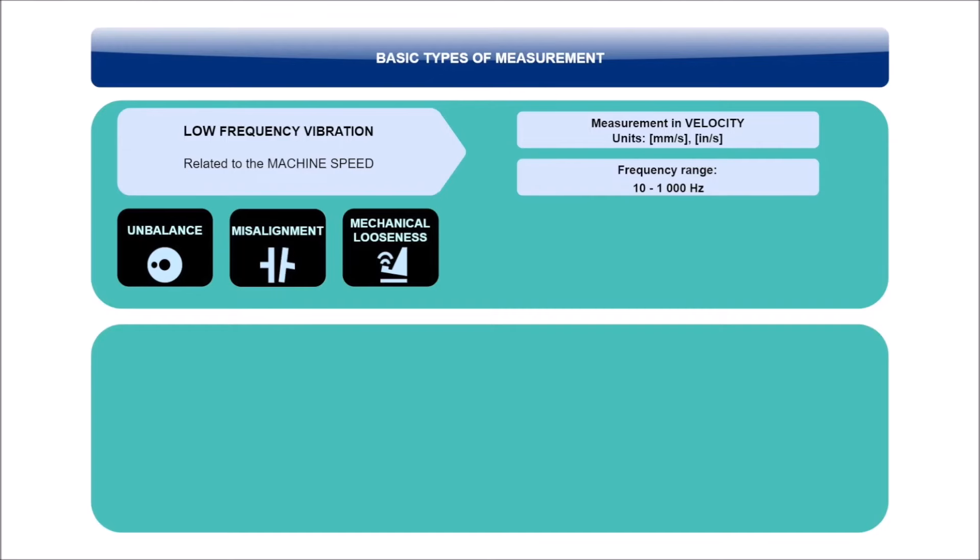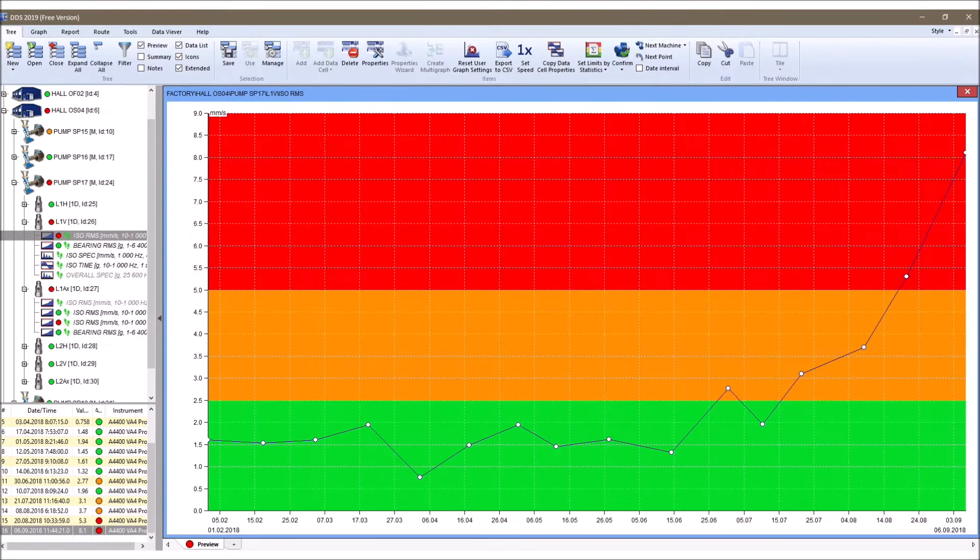This way we came to the conclusion that to monitor mechanical vibrations related to the shaft speed of the machine, we will use the measurement of overall velocity in millimeters per second or inches per second in the range of 10 to 1000 Hz. This measurement is represented by one number. Using the ADASH DDS software, we can trend this value in time and see its development.